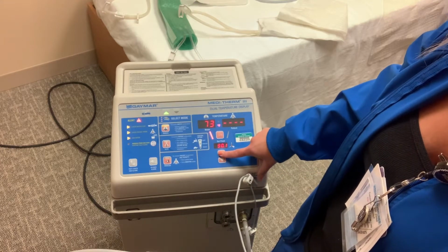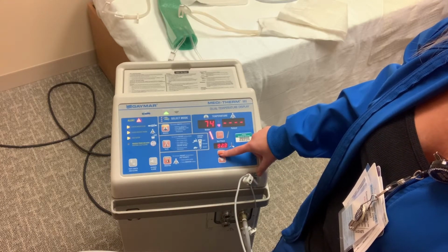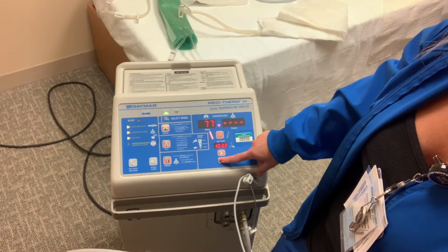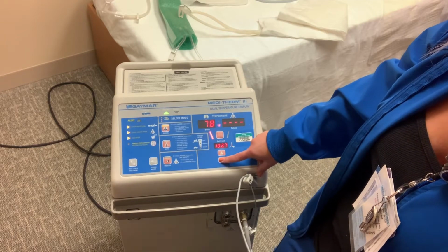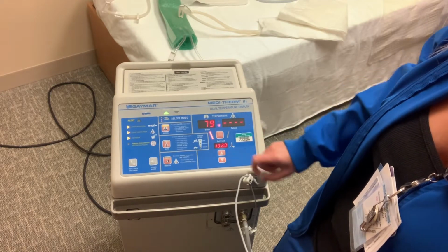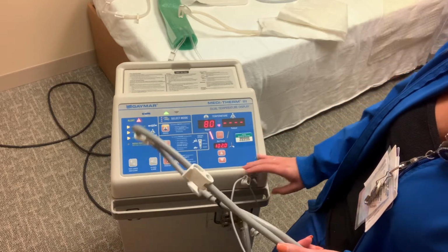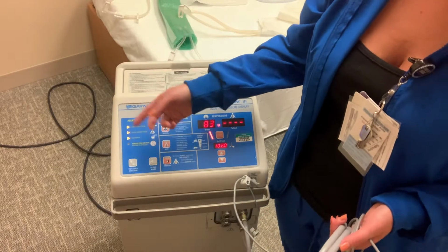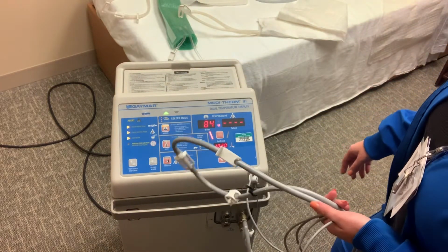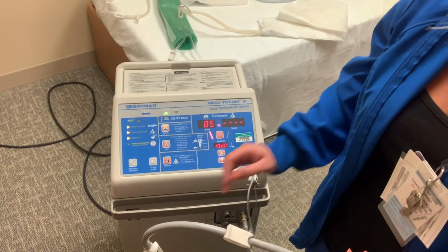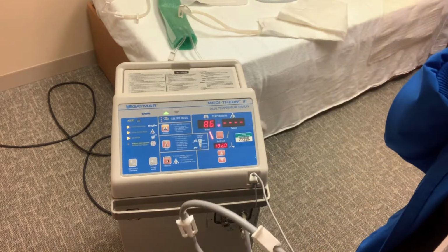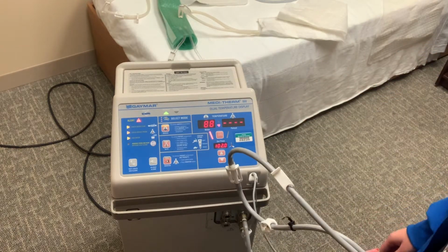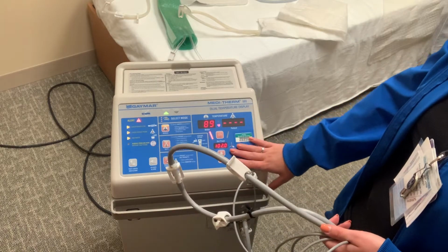So we're going to go ahead and set this to 102. Alright, so you're going to set this to 102. Please make sure that when you are attaching the blankets, whether it be the green blanket or the disposable blankets, you do have some sort of barrier in between the patient, whether that be a sheet or something like that. A sheet would probably work the best because it'll still protect the patient but still allow the heat to be transmitted through there. So you're going to set this to 102.